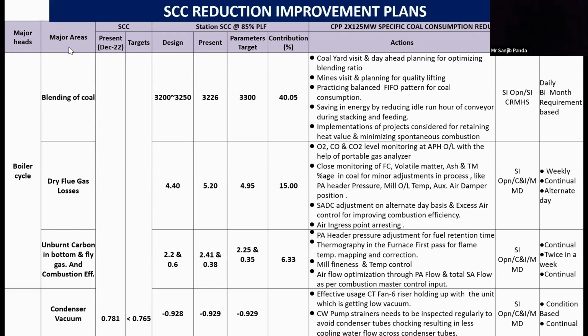Close monitoring of FC, volatile matter and moisture percentage in coal for minor adjustments in process like PA header pressure, mill outlet temperature, auxiliary air damper position, etc. SADC adjustment, air ingress point arresting. With regards to unburnt carbon in bottom and fly ash, PA header pressure adjustment, thermography in the furnace first pass for flame temperature mapping and correction, mill fineness and temperature control, airflow optimization through PA flow and total secondary airflow are being done. And then for condenser vacuum, effective usage of the fan, holding up with the unit which is getting low vacuum, CW pump strainers inspection regularly to avoid condenser tubes choking.